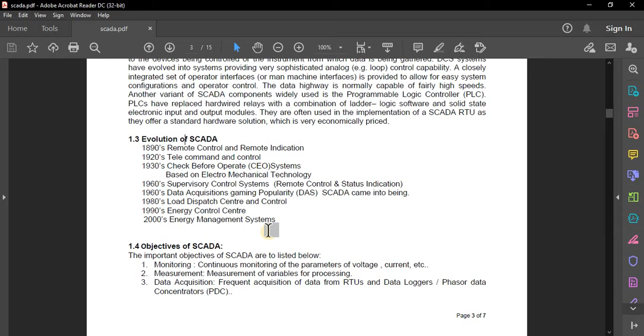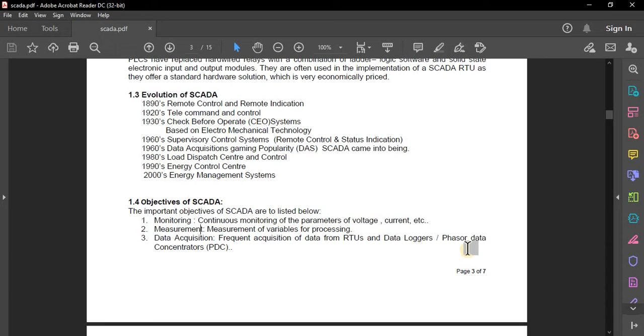So the objectives of SCADA. There are different objectives or goals of a SCADA. First one is monitoring, so continuous monitoring of the parameters of voltage, current, etc. Then measurement of variables for processing, and then data acquisition, so frequent acquisition of data from remote terminal units and data loggers or sensors or phasor data concentrator, etc. Next one is data communication: transmission and receiving of large amounts of data from field to control centers. That is what SCADA needs to do. Then control, so online real-time control for closed loop and open loop process. And then the last one is automation, so automatic task of switching of transmission lines, then circuit breakers, etc.